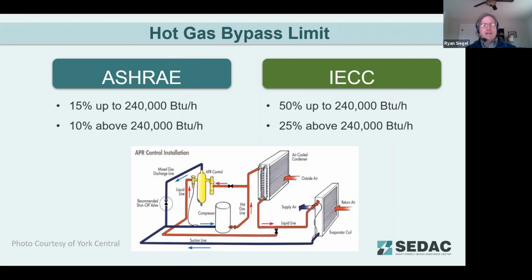This is something that again, we're seeing more and more equipment manufacturers trying to reduce how much they use hot gas bypass for capacity control and trying to use alternate methods. And some of this is also, as we're seeing more variable speed compressors and much more variable refrigerant flow systems going in, they have much better capacity control rather than just using hot gas bypass. Because really what you're doing is you're just giving up some of that work that you did to compress that refrigerant, and then just releasing it is not terribly beneficial.